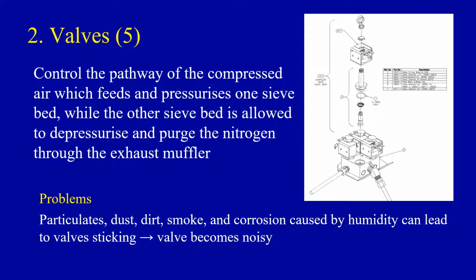And it's very important that we keep an oxygen concentrator clean. If you don't keep it clean, then dust and dirt or particles can get into the concentrator, and they can lead to the valves getting stickier. And if they're sticky, then the gas doesn't move through the concentrator like it should. The valves then become noisy, so the concentrator makes more noise, and also it can lead to a reduced concentration of oxygen being produced by the machine.